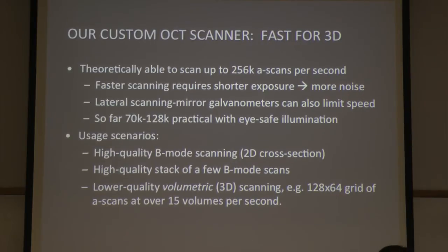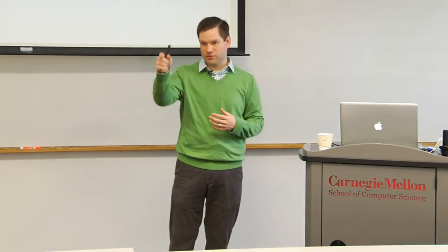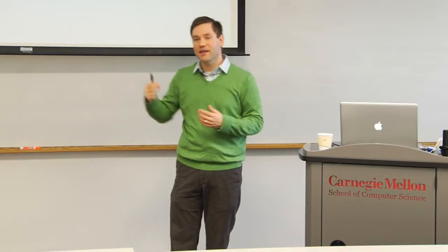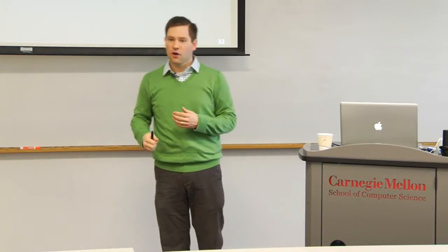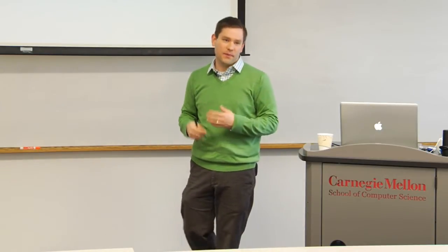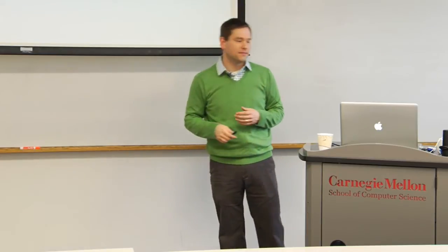Now, this isn't like what you would be using with your typical laser rangefinder from SICK that is going to be giving you 2.5 dimensions, where it gives you a depth distance to the first target at every point. This is an OCT image. It's volumetric. We have data at every single point in space over that entire 6 millimeter range. Our pixels are basically 6 microns apart.